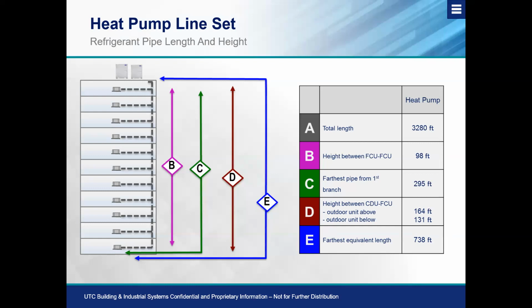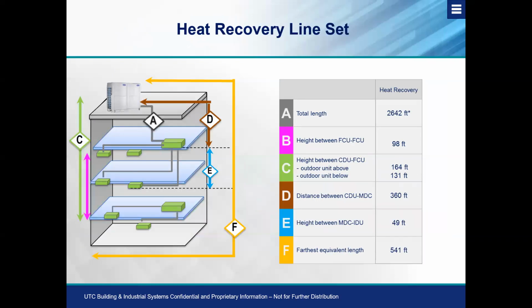So the generalized rule of thumb: our total system piping length for a heat pump carrier style system is 3,200 feet. Same thing applies with heat recovery in terms of running the application. As a general rule of thumb, the total length that we can operate with a variable heat recovery system is 2,640 feet.